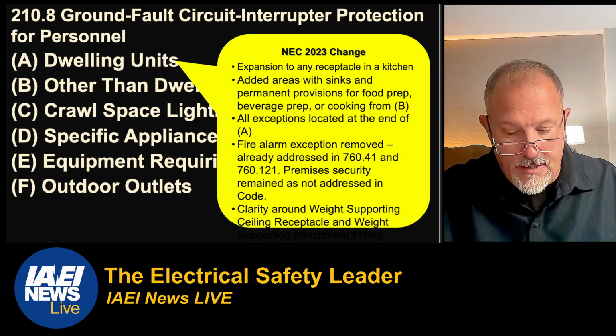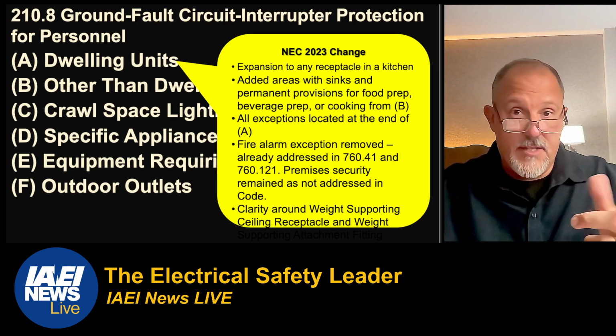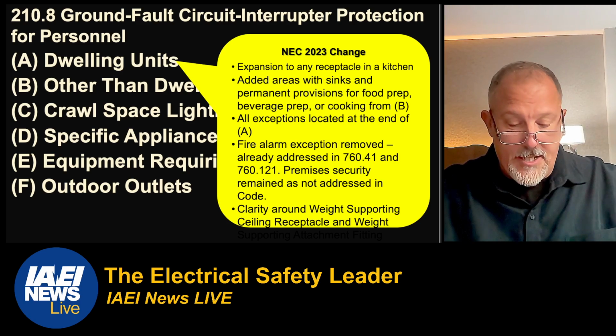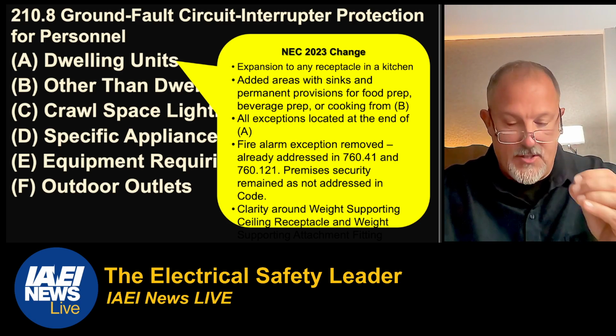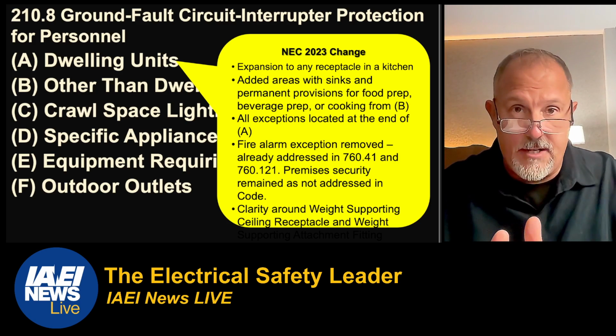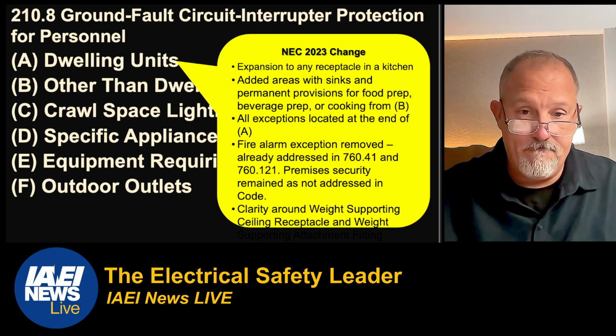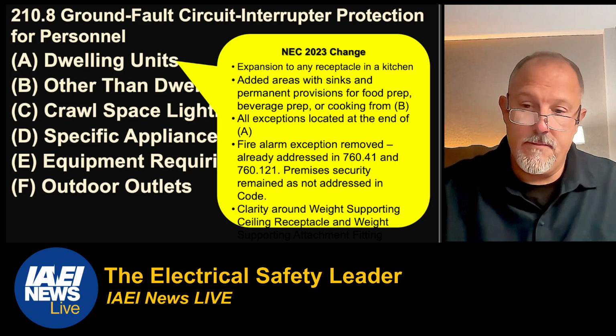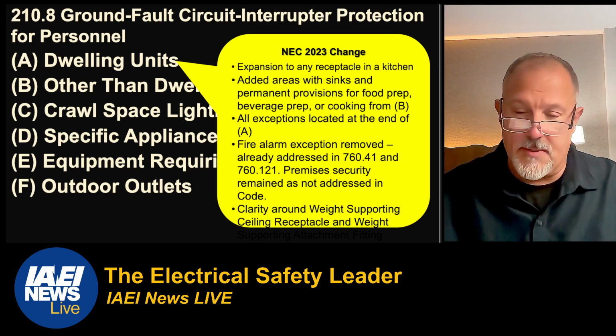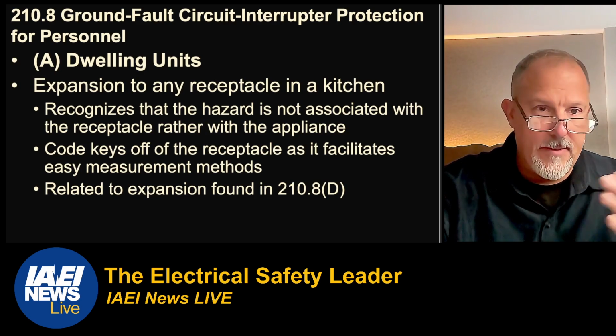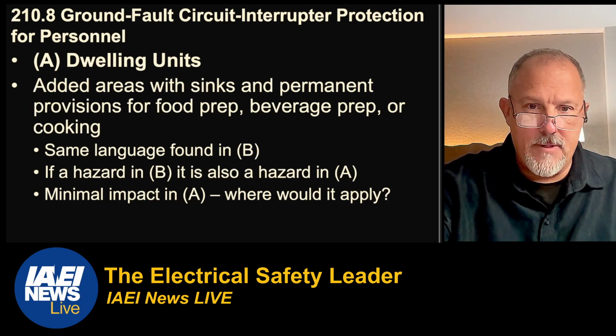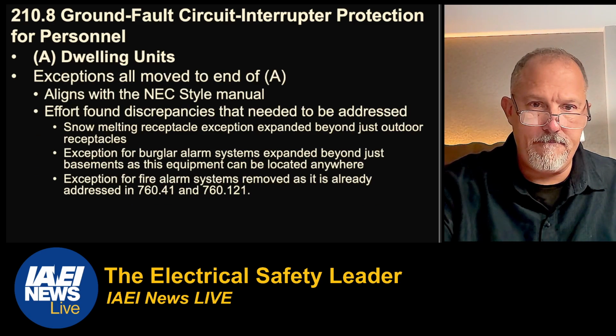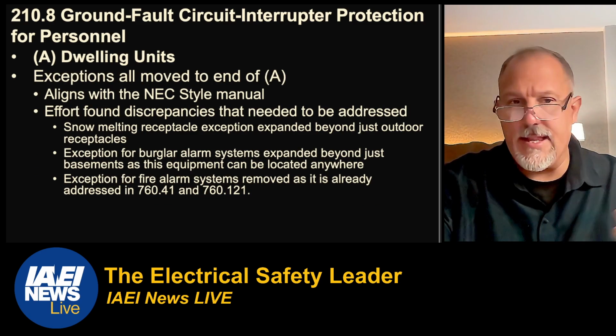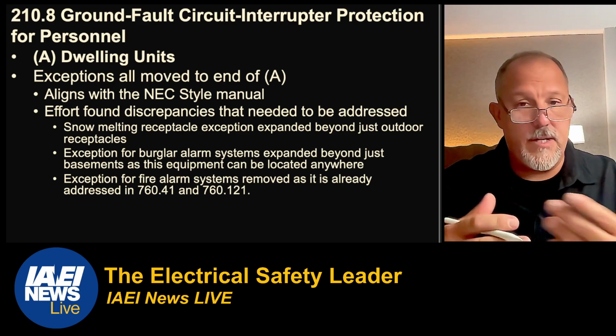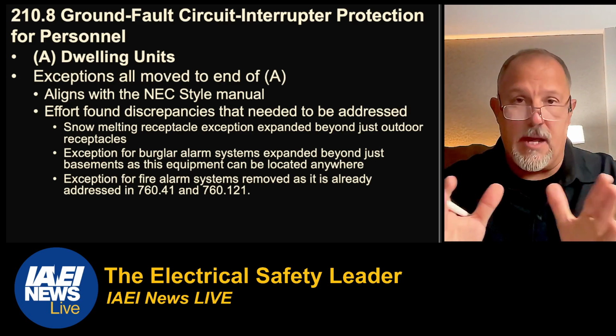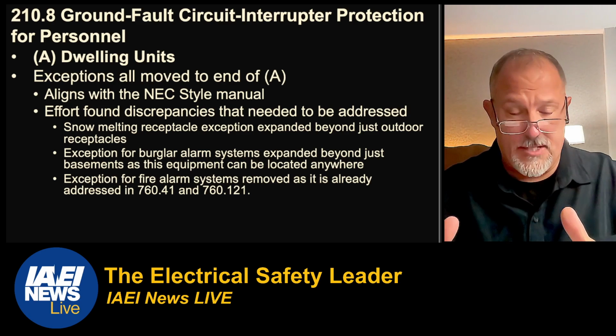And I believe, I would say out of all of those, significant change, kitchens. Expansion in kitchens, that's the one that I would argue is the significant change in 210.8(A) for dwelling units. So all receptacles, and that picks up any of those appliances, anything that's plugged in. All right, so we already talked about this. Already talked about that. Moving the exceptions to the end. That was a style manual thing, NEC style manual. And it streamlined those exceptions as well. And it expanded those exceptions.